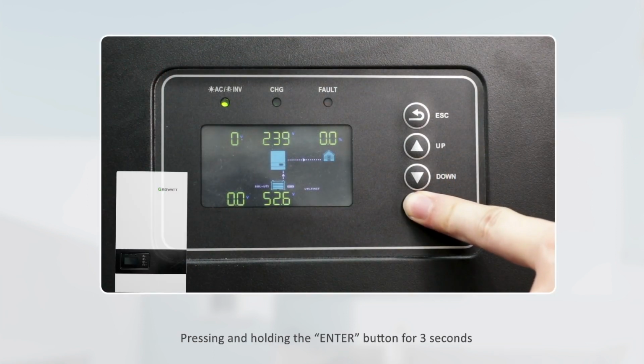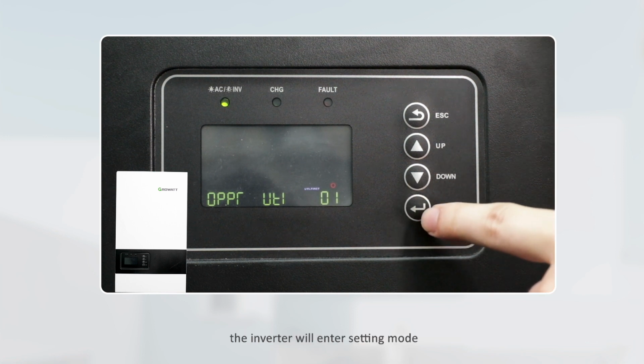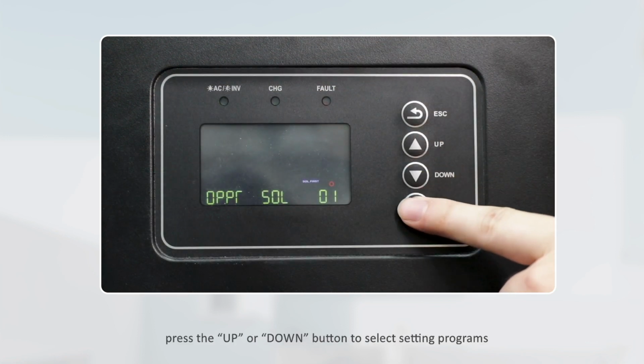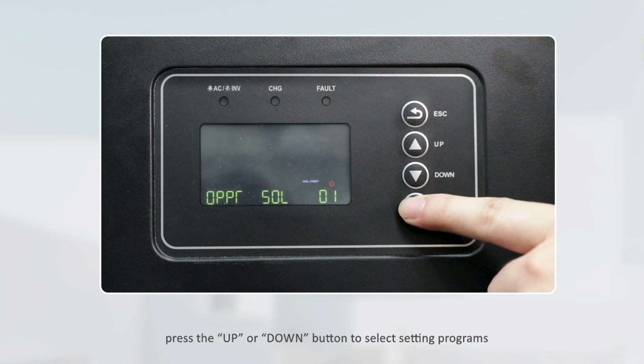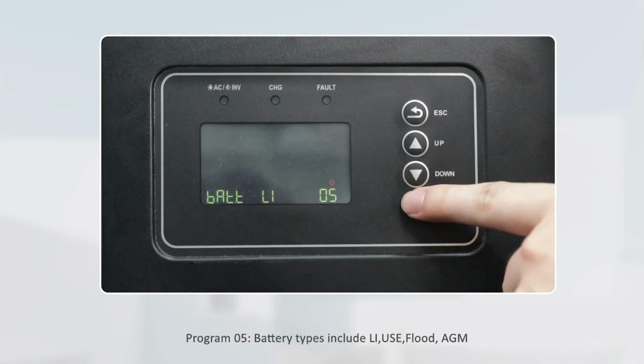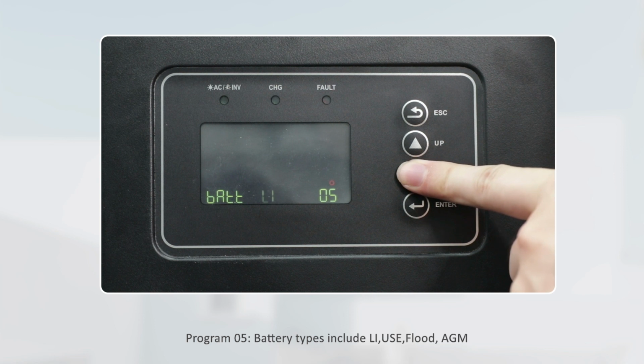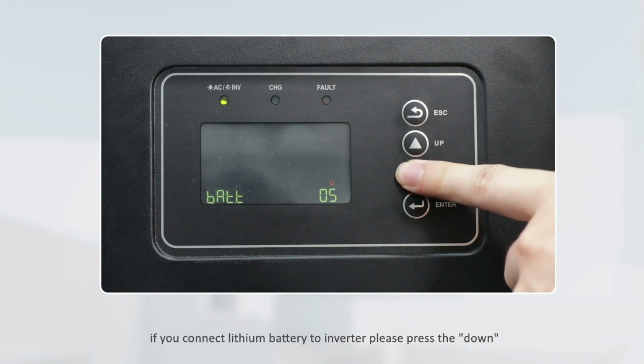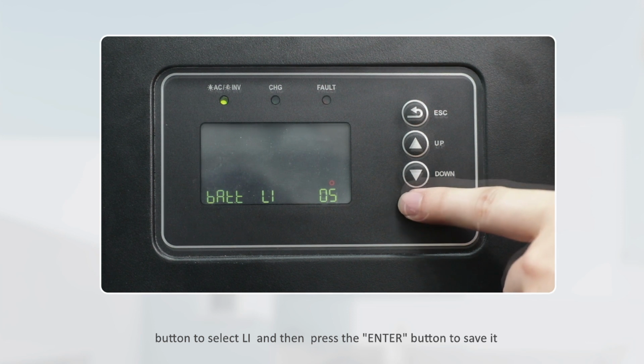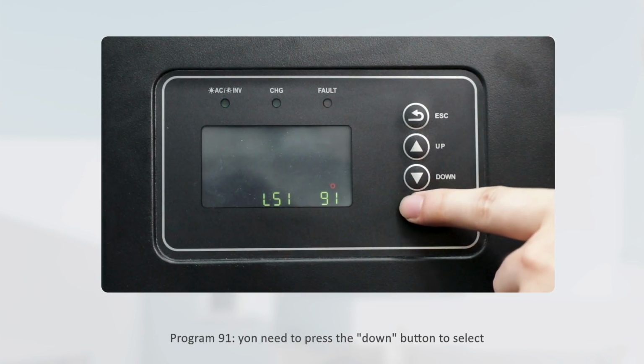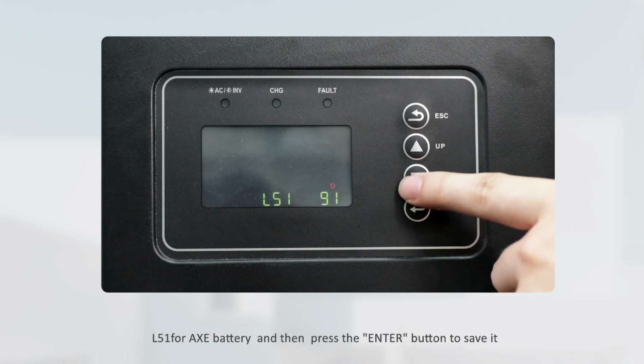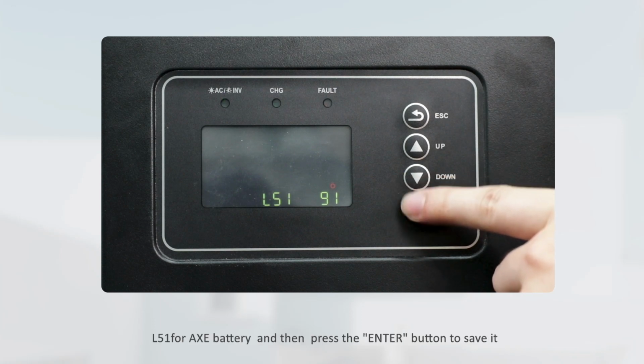Pressing and holding the enter button for 3 seconds, the inverter will enter setting mode. Press the up or down button to select setting programs. Program 05, battery types include LI, USE, Flood, AGM. If you connect the lithium battery to the inverter, please press the down button to select LI and then press the enter button to save it. Program 91, you need to press the down button to select L51 for the AXE battery and then press the enter button to save it.